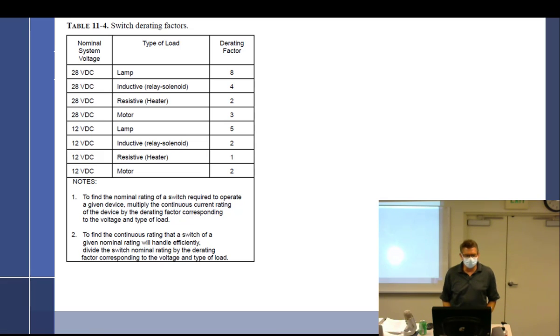11-4, all right, derating factor. Nominal system voltage - remember, nominal means 28 or 24, it means about that. So if I have a lamp in a 12 volt system, I'm at a derating factor of 5. Inductive solenoid relay, which pretty much all relays are, factor of 2, because a relay has a coil in it. A coil is inductive, it has a high inrush of current. A heater, I think that would be more, but okay, it's just a big resistor I guess. And then a motor, 2. So a derating factor of 3, derating factor of 2.